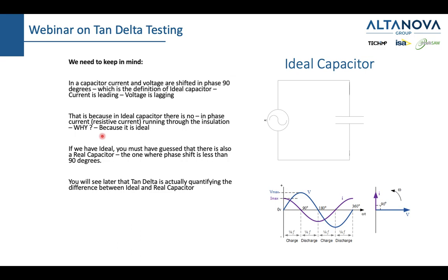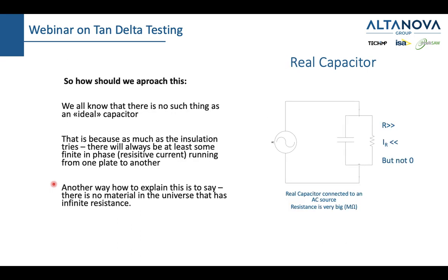We will introduce the concept of a real capacitor. The real capacitor differs from an ideal capacitor in that there is not a 90 degrees phase shift between current and voltage. It is less than 90 degrees. So later on you will see that the tan delta is quantifying the difference between the ideal and the real capacitor. So what is this real capacitor?